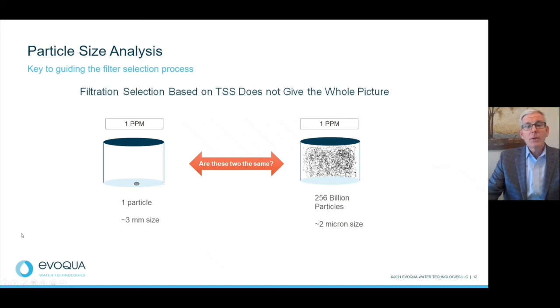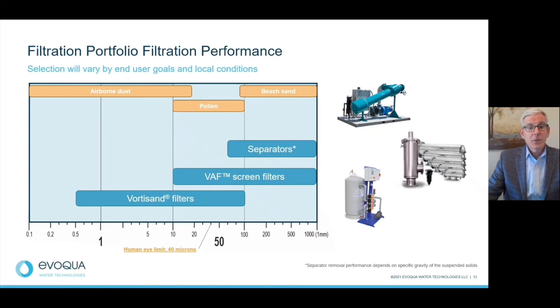Side stream filtration is an integral part of reducing water used in cooling tower systems. And side stream filtration is again recommended by the Cooling Tower Institute. The only way to truly know what the right filter is in your system is to do a particle size distribution analysis. This analysis is done in a lab and will tell you the size and volume of the suspended solids in your system. Now, I've been involved in many particle size studies, and I'm pretty confident that you will find that nearly 90% of the particles in your cooling tower water are less than 1 micron. Now, most common side stream filters only remove down to 15 microns, allowing everything else to remain in the system. But as you can see by this slide, Evoqua's Vortisand filter can remove down to 0.5 microns. This filter can potentially remove over 90% of the particles found in your cooling water, greatly reducing your chemical demand.